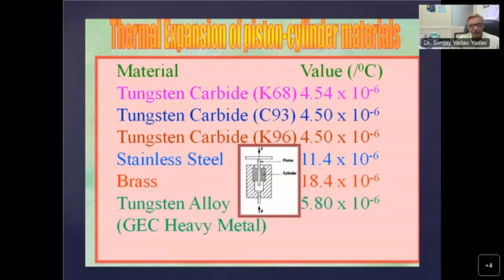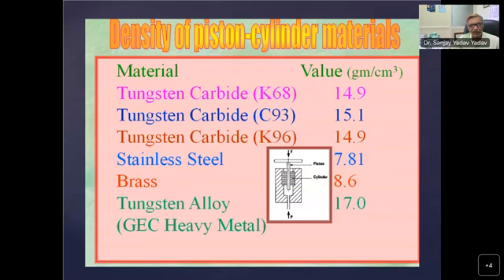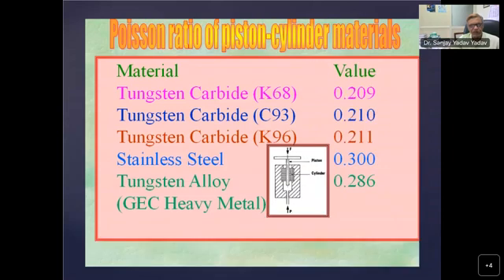These are the thermal expansion coefficients of the piston cylinder assembly applied in pressure correction, with different values. Normally, tungsten carbide and stainless steel are used in a dead weight tester, but sometimes other materials are being used. This is the piston cylinder material. Again, some material. Poisson ratio.